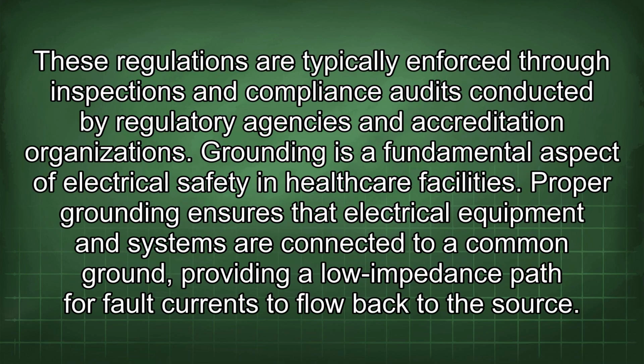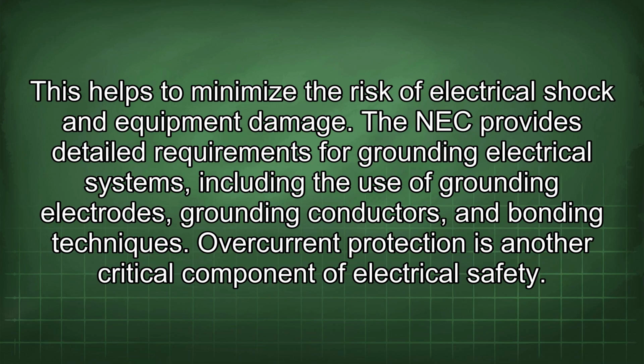These regulations are typically enforced through inspections and compliance audits conducted by regulatory agencies and accreditation organizations. Grounding is a fundamental aspect of electrical safety in healthcare facilities. Proper grounding ensures that electrical equipment and systems are connected to a common ground, providing a low impedance path for fault currents to flow back to the source. This helps to minimize the risk of electrical shock and equipment damage. The NEC provides detailed requirements for grounding electrical systems, including the use of grounding electrodes, grounding conductors, and bonding techniques.